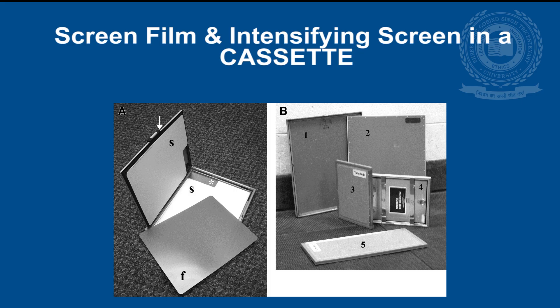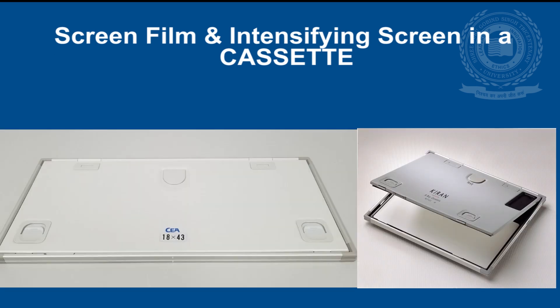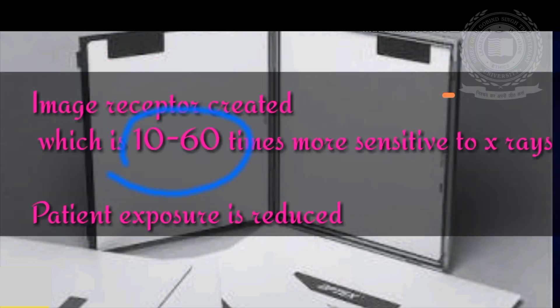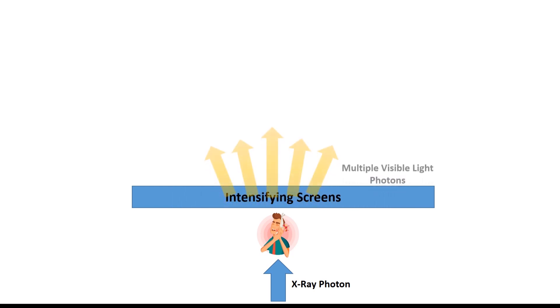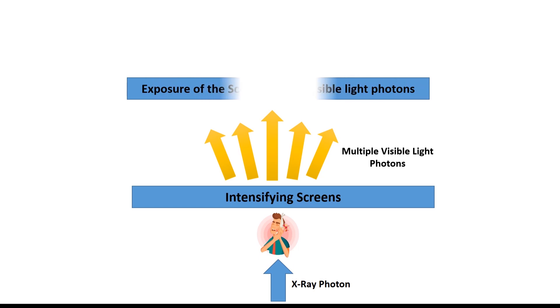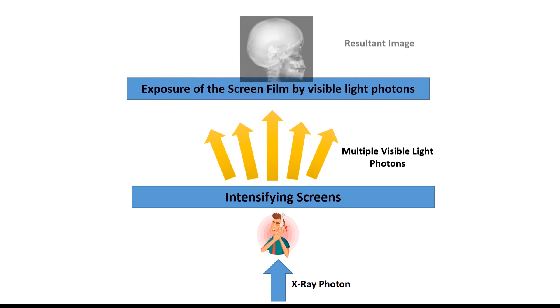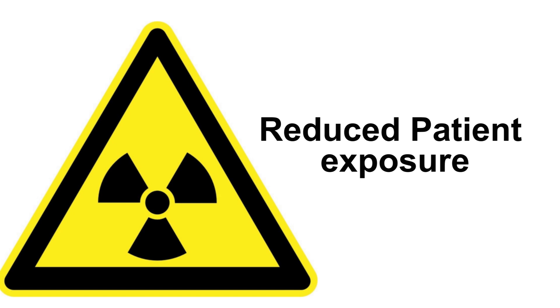The image receptor system used in extraoral radiography is composed of screen film and intensifying screens. This creates an image receptor system which is 10 to 60 times more sensitive to x-rays than the film alone, because one x-ray photon that falls on the screen is converted into 4000 visible light photons which then exposes the film. Thus, this image receptor system greatly reduces the patient exposure.